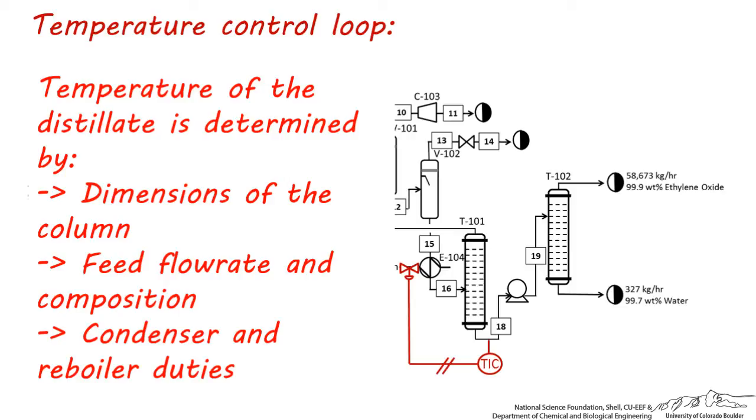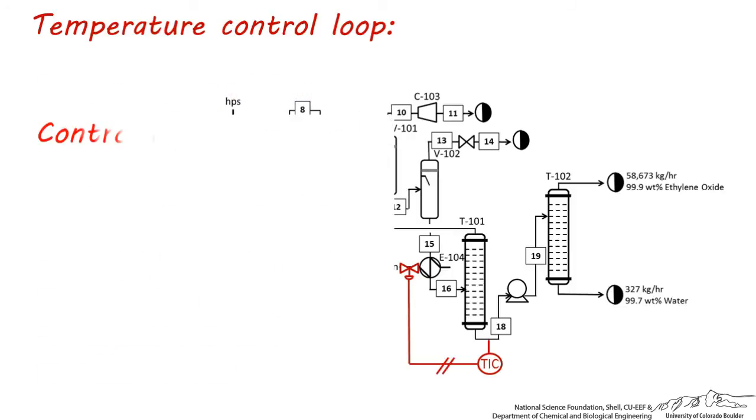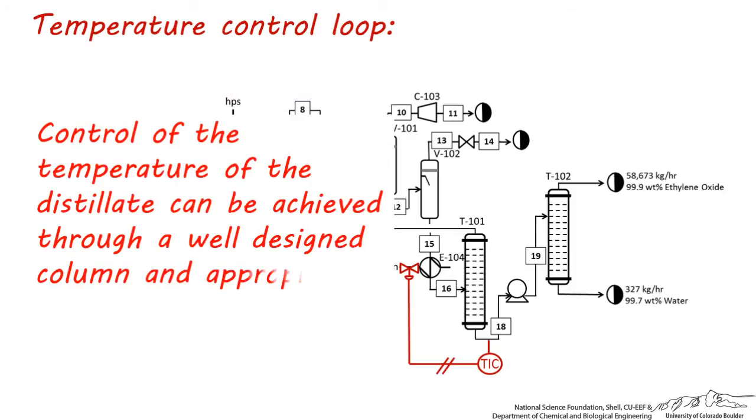Also, this control loop is receiving its signal from the reboiler, which is excellent for reboiler control, but it doesn't help control the distillate temperature directly. So not even this shorter control loop is the best option. It's best to have a well-designed column with an appropriately sized condenser.